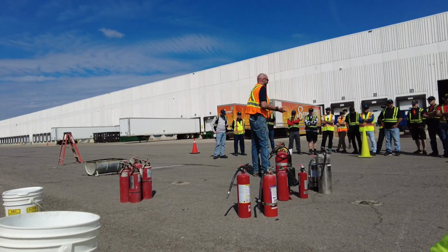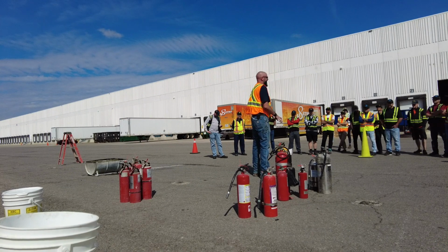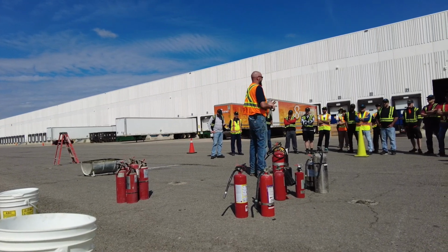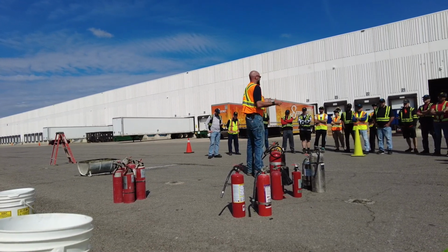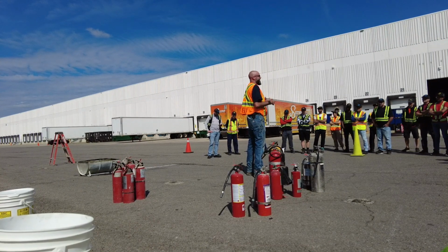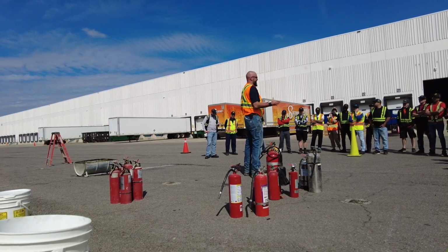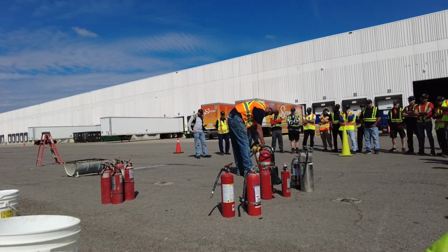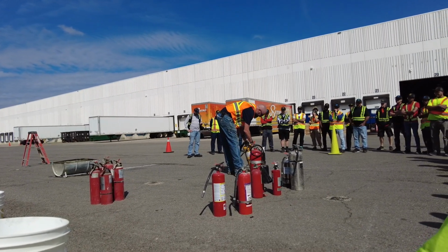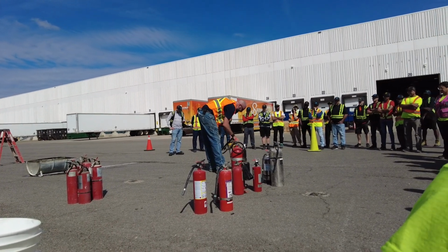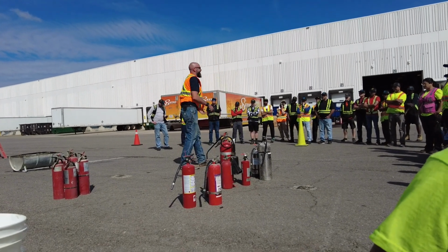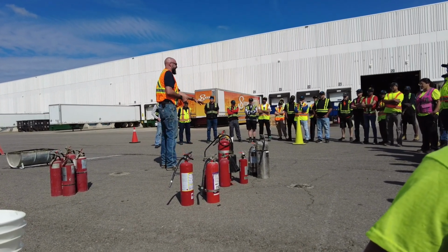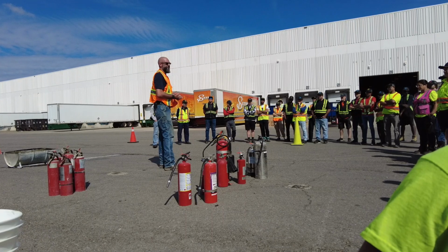So, truly and honestly, this is the only size, this is the only color they come in so that they stand out. Your reactive metal fires are very intense fires. And if you look at the chart on the back here, magnesium chips, I'm allowed 4 square feet or 6 pounds of material. That is all that 30-pound extinguisher can deal with.